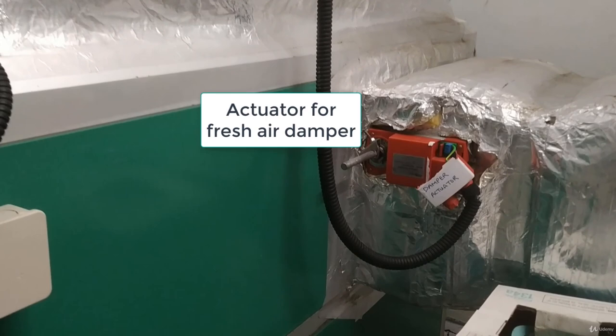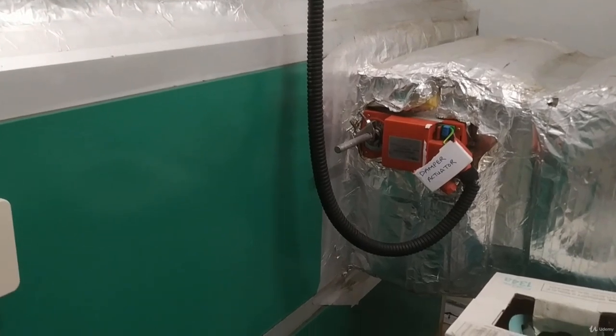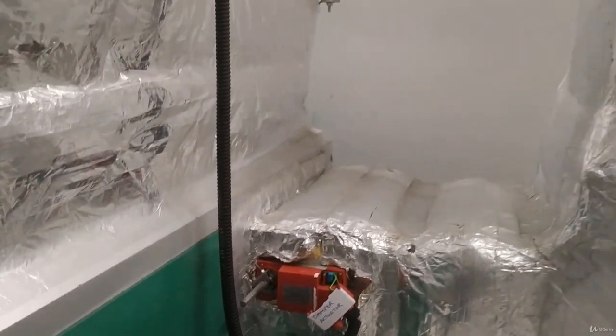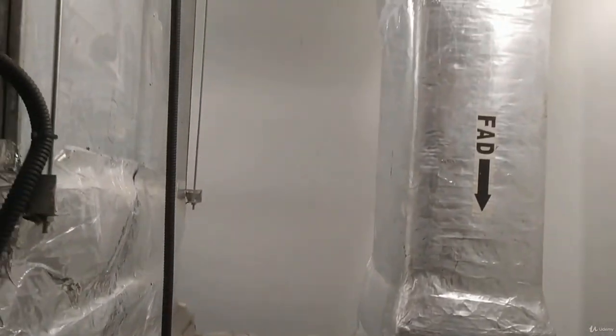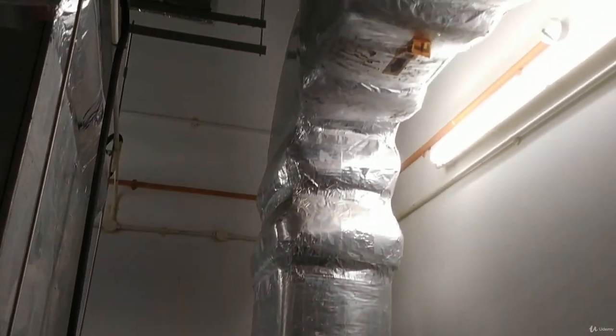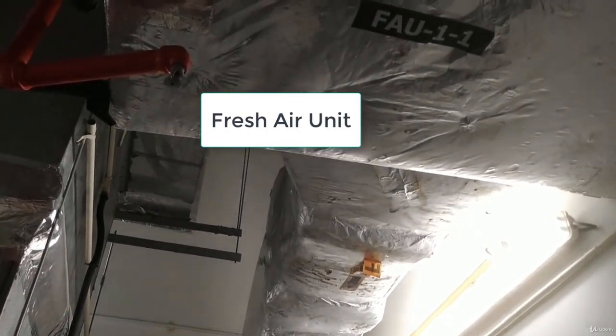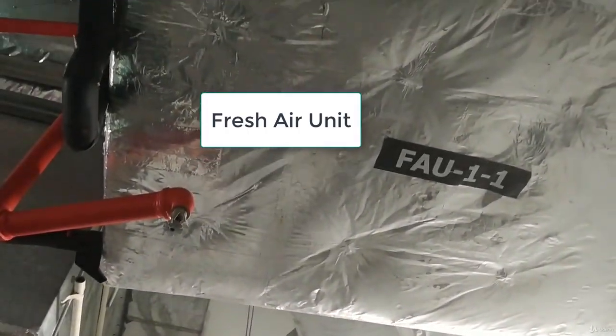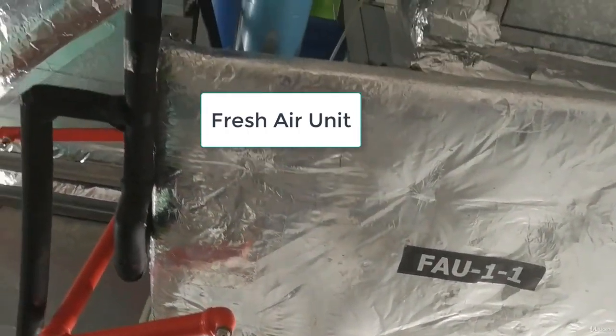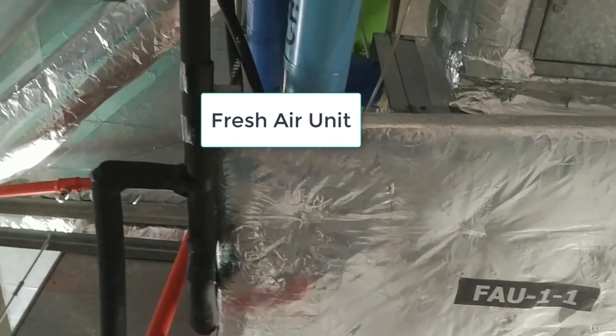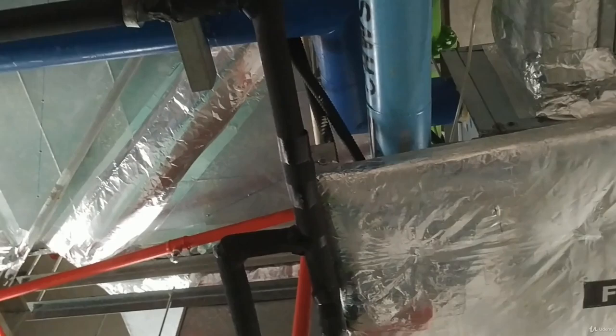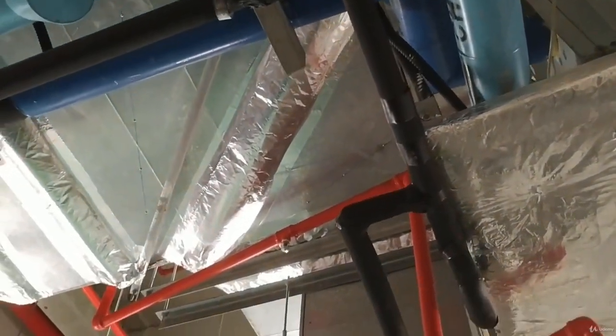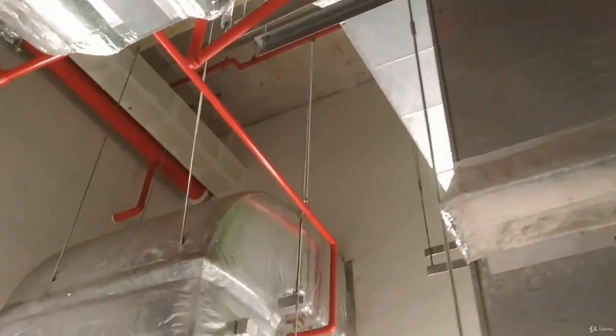The fresh air damper, which is controlled by the actuator here, will only open up when there's a need to reduce the carbon dioxide level in the space. For some AHU, the fresh air will get treated first before going into the main AHU, and it is done at a smaller unit like this called the fresh air unit. The fresh air will pass through the cooling coil in the fresh air unit first to reduce a certain amount of heat, and that will help to reduce the burden on the main AHU.